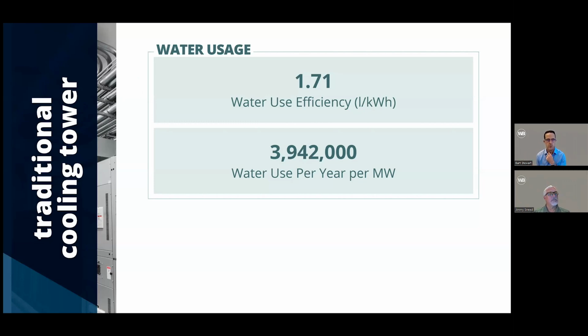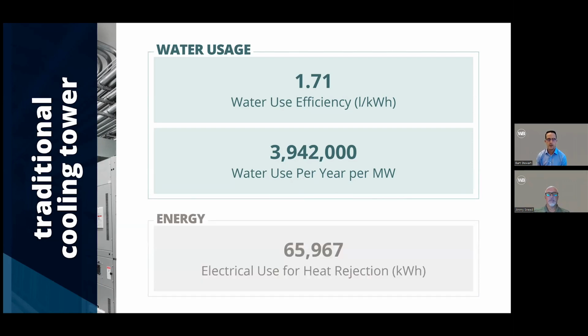This is almost 4 million gallons of water per year per megawatt. So if you look at that over the course of a day for 50 to 100 megawatt facilities, numbers of 500,000 to 1 million gallons of water a day are real. And the fans on it use about 66,000 kilowatt hours of electricity per year.